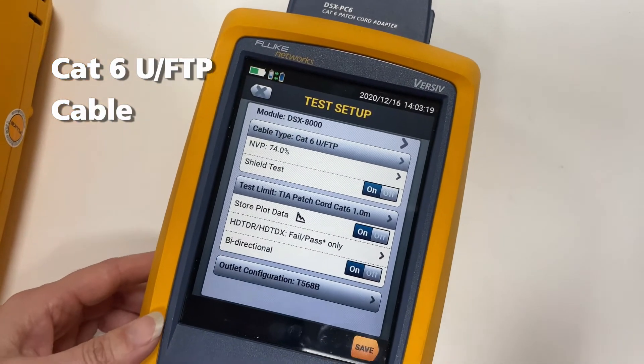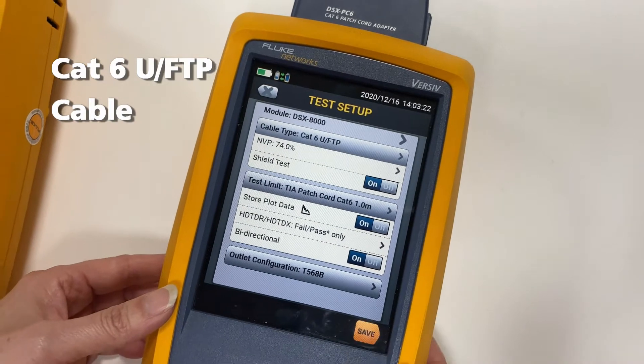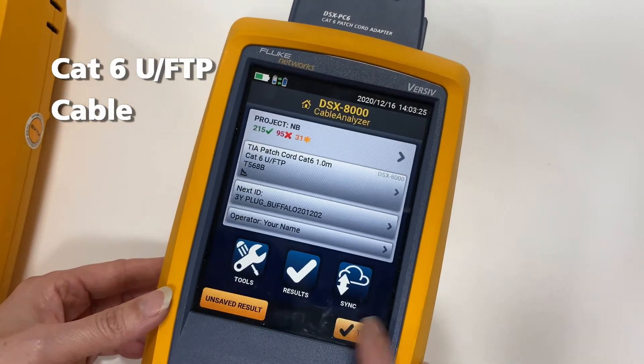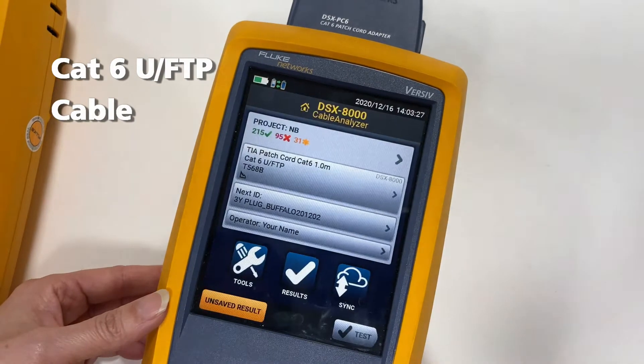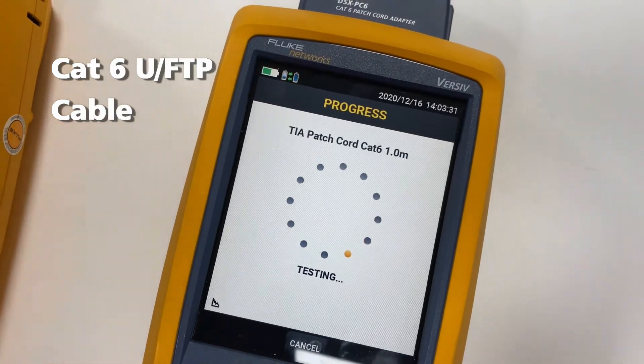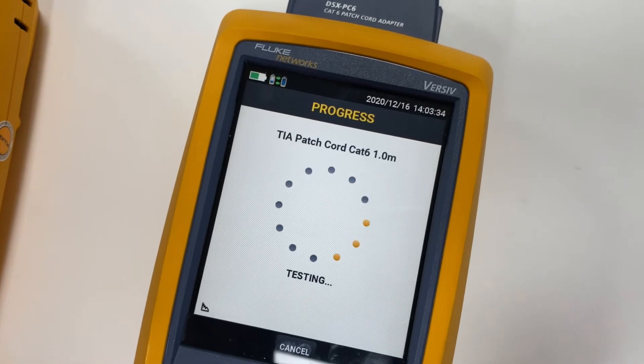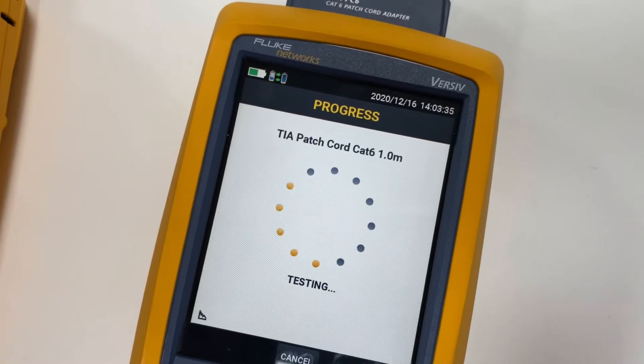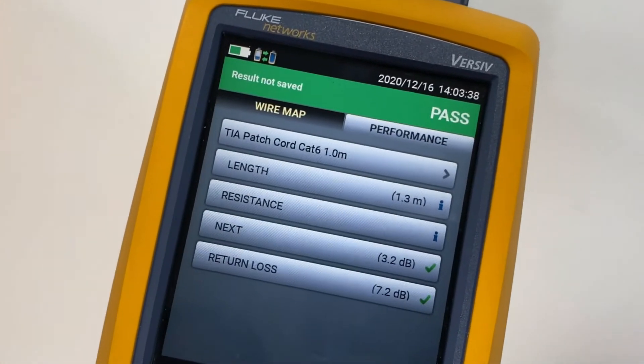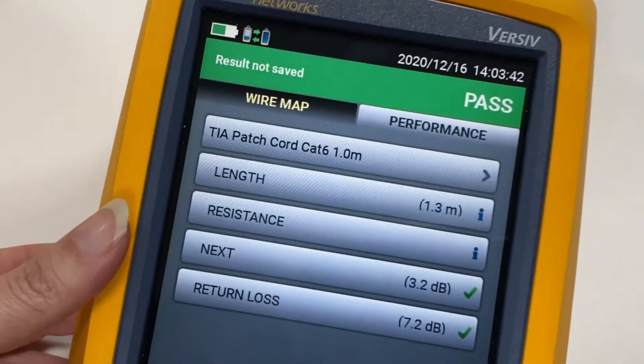Now we start the test. We got the test result — NEXT is 3.2 dB. It passed the component test.